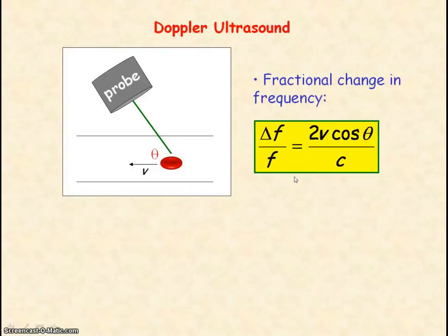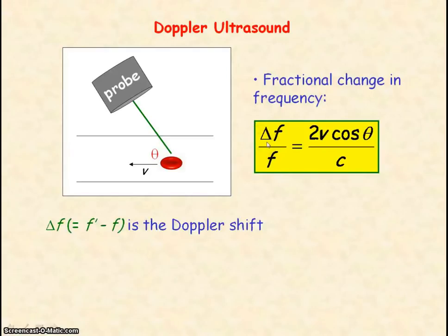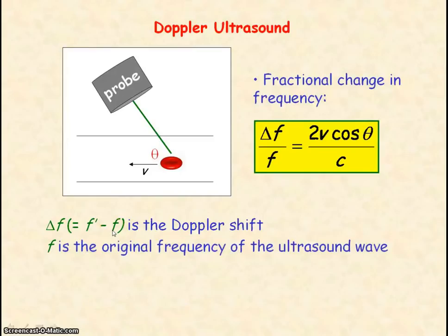This equation can be used to measure the speed of blood, where delta f divided by f represents the fractional change in frequency. Delta f is the change in frequency — the Doppler shift — equal to f prime minus f. F prime is the frequency of the ultrasound detected by the probe, and f is the original frequency emitted from the probe. The factor of two in the equation accounts for the double Doppler shift: the change in frequency for the incident wave as well as for the reflected wave.